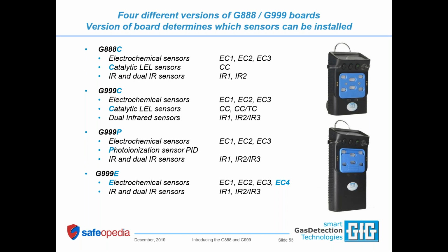One of the attendees has asked, can the G999 run both a PID and a standard catalytic LEL sensor? No, we are going to stick with IR LEL when we have a PID sensor installed in the 999. The reason is that the IR LEL sensor is a better choice for the larger hydrocarbon and VOC molecules that you are typically measuring with the PID. The PID picks up what's going on in the ppm range, and the IR LEL sensor is going to pick it up in the percent LEL range.